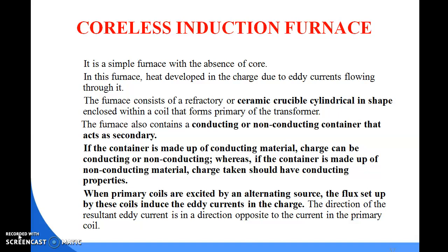The furnace also contains a conducting or non-conducting container that acts as a secondary. If the container is made up of conducting material, the charge can be non-conducting or conducting. Whereas if the container is made up of non-conducting material, the charge taken should have a conducting property. When the primary coil is excited by an alternating source, the flux set up by this coil induces eddy current in the charge. The direction of the resultant eddy current is opposite to the current in the primary coil.